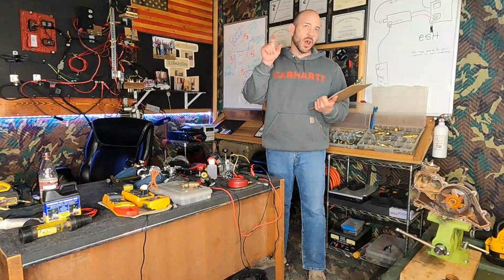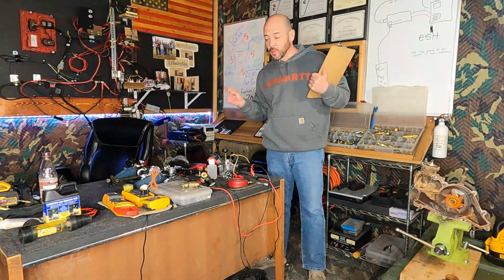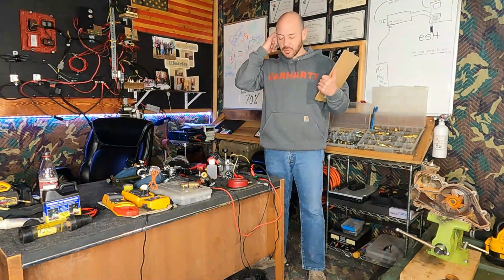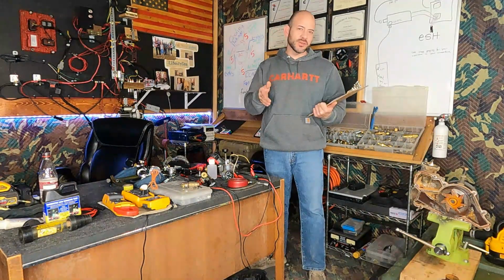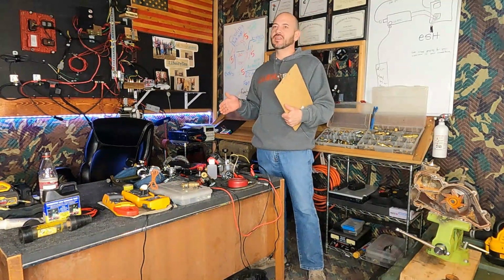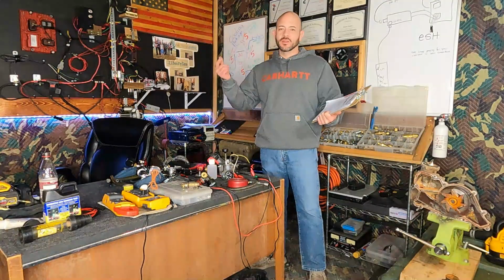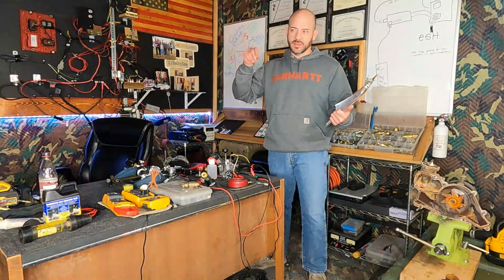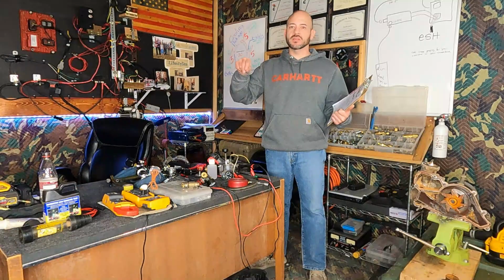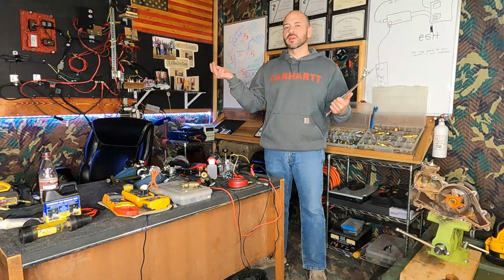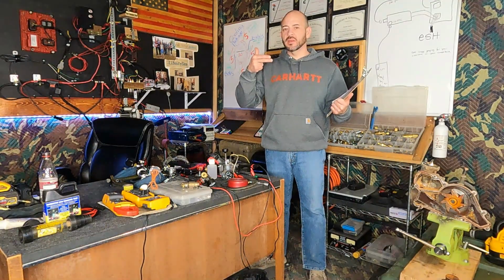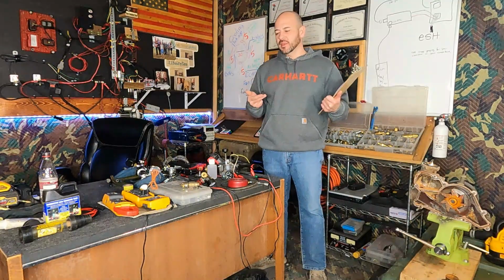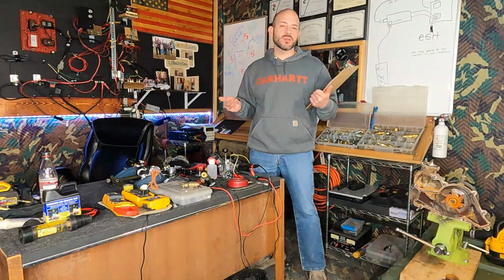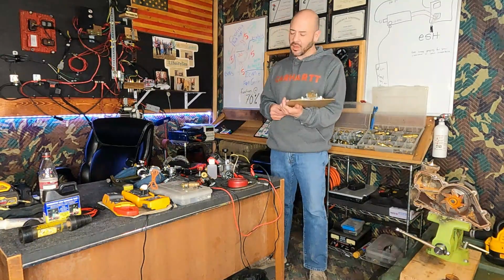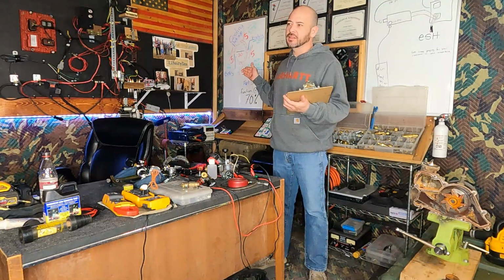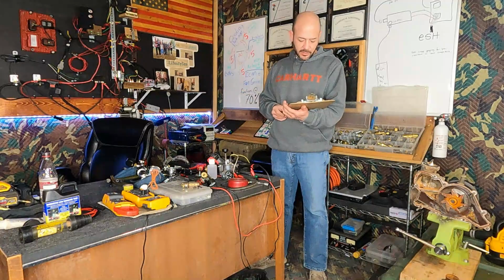Now, some have a thermal probe, but also a motor. Like I said, there are so many ways to run a fan—you really have to know how a particular fan is run instead of assuming they're all done the same. Look at your specs and see: is this fan shut off with the solenoid on? Is air normally going through it? Is it a normally open solenoid, or normally closed? These are things you cannot troubleshoot unless you know. That's why I talk a lot about electrical and mapping circuits.